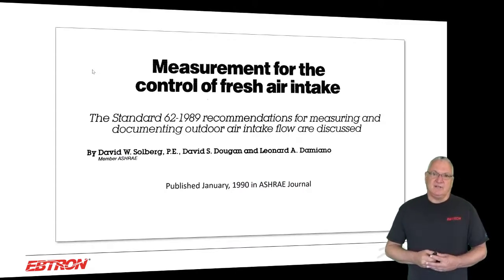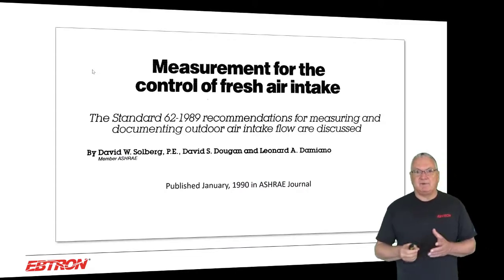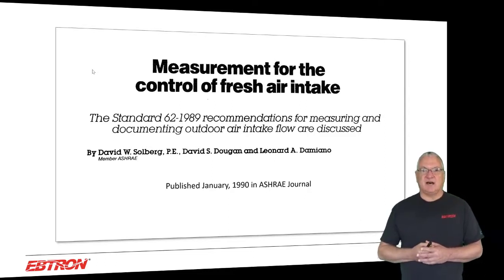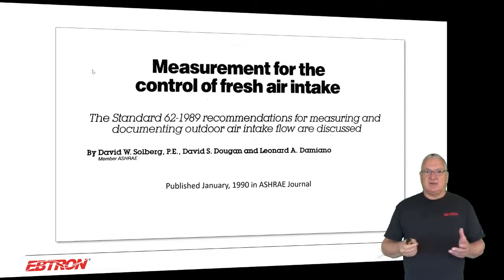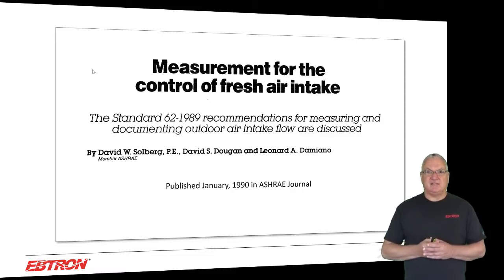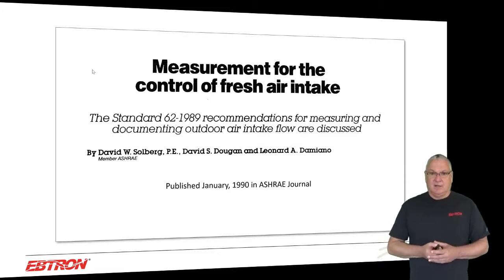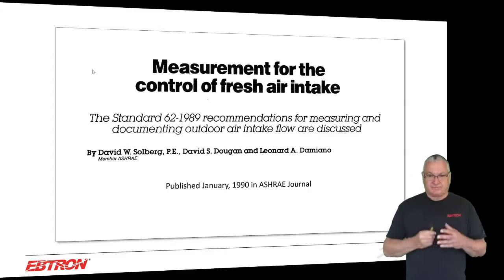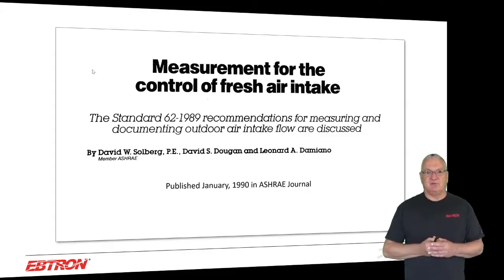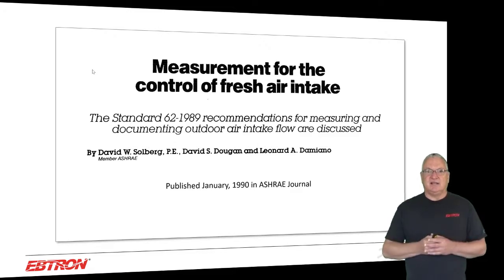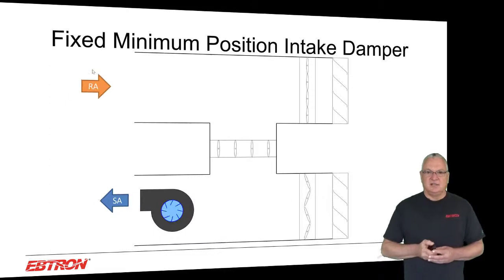I'm going to date myself a little here, but this paper really changed things. I started back in the eighties at Ebtron, and back then everybody was setting fixed minimum position dampers on VAV systems. As the VAV systems turned down, the ventilation rates turned down and we had an air quality problem. This paper was published in January 1990, by David Solberg, myself, and Len Damiano. David Solberg was the real brains behind it — Len and I kind of went along for the ride. But it's a really good paper, and it's still relevant 30 years later.